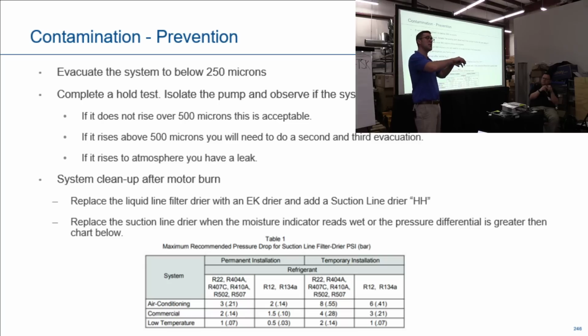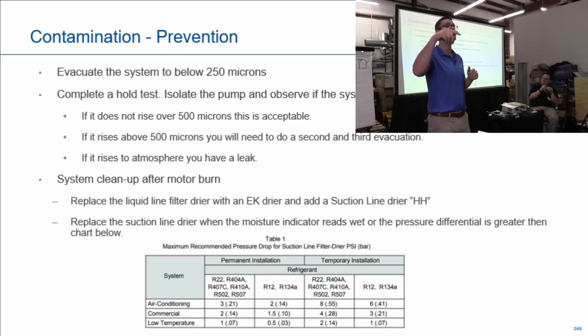You're right at the compressor now with a filter dryer, and all of a sudden your compression ratio, that starts to block up. Your compression ratio gets higher. And what did we say about compression ratio? It adds heat. Yeah, go ahead.